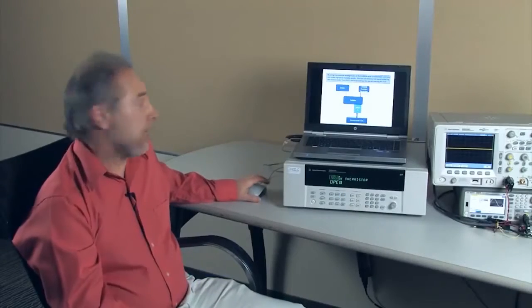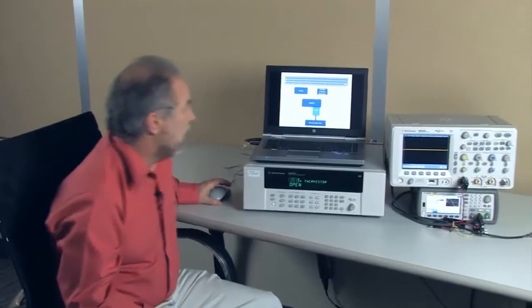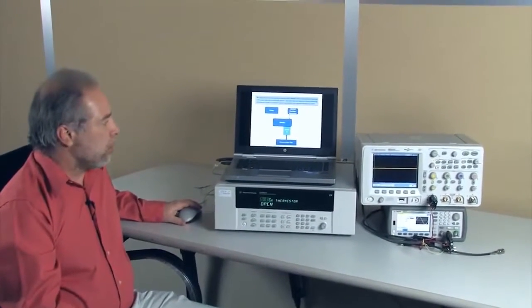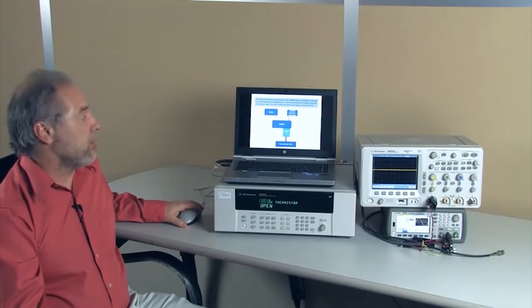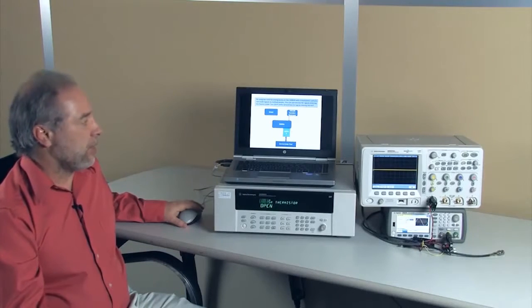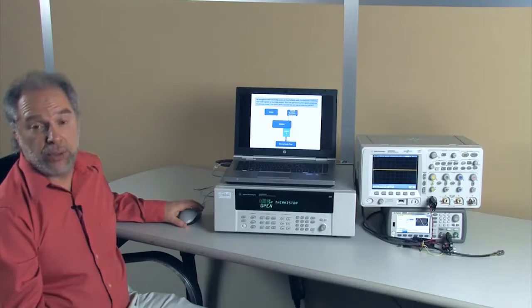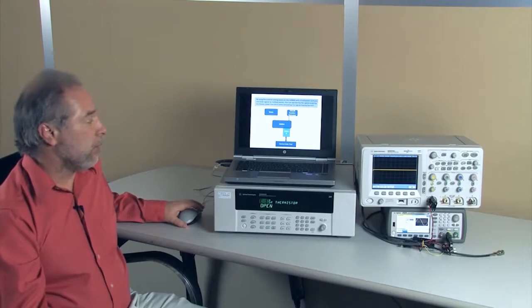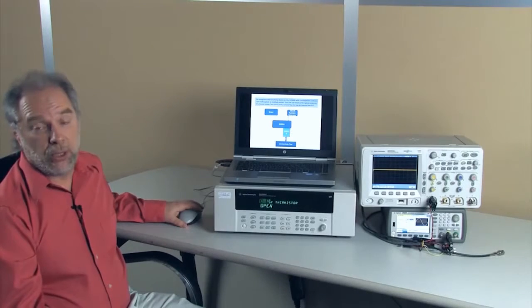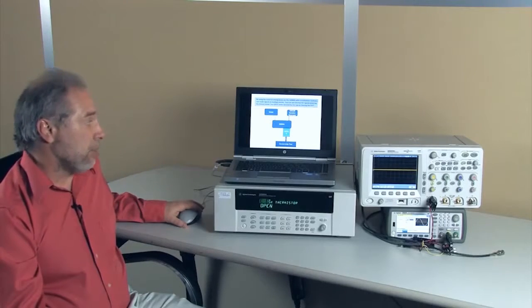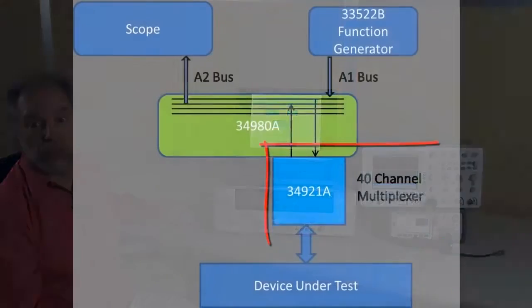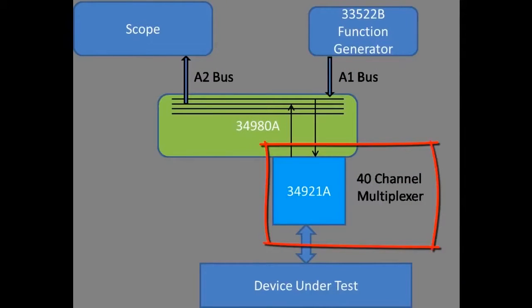When you are testing a device under test, you normally have multiple locations on the device that you want to either inject a signal into or measure a signal. One of the ways to look at all of those different points is to use a multiplexer card. In this case, we use the 34921, which is a 40-channel multiplexer card that's plugged into the 34980.